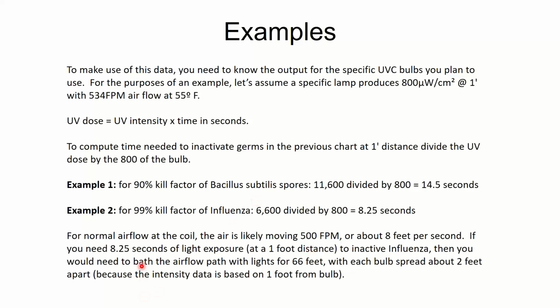To get 8 seconds of shine time at a 1 foot distance, I'd have to bathe the airflow for 66 feet, putting a bulb every 2 feet to get enough shine time to kill 99% of influenza on the first pass. Well, I don't have 66 feet to work with, and I'm not going to buy 33 bulbs to put in 66 feet of ductwork. That's just not happening. So it's going to be very difficult to kill bacteria and flu in the air this way.